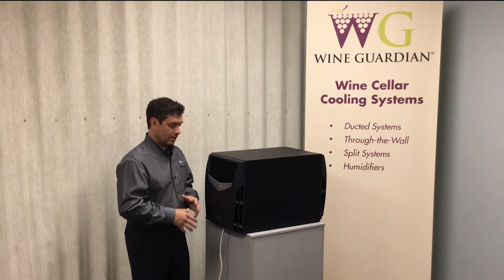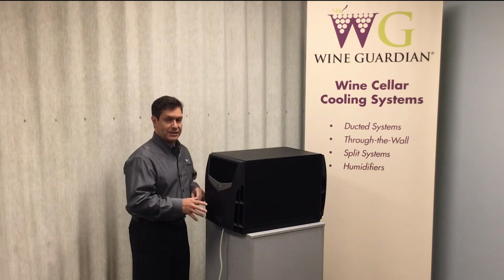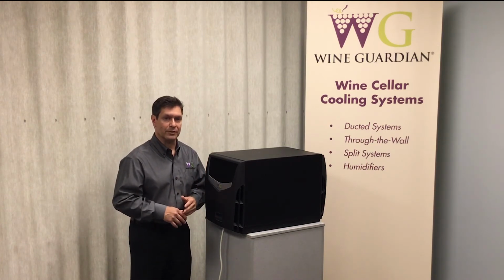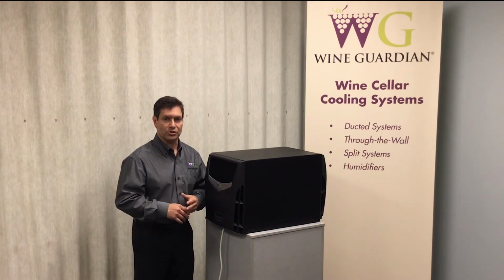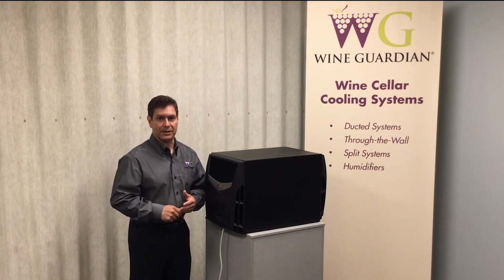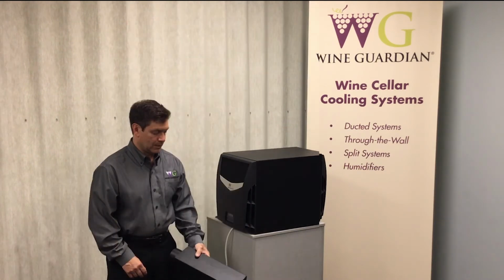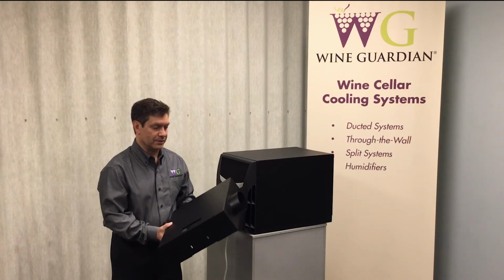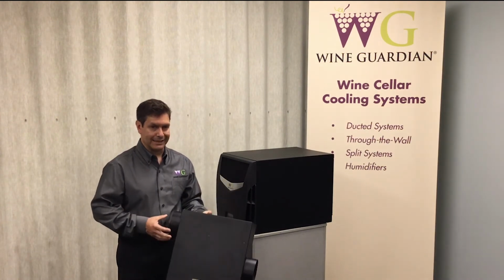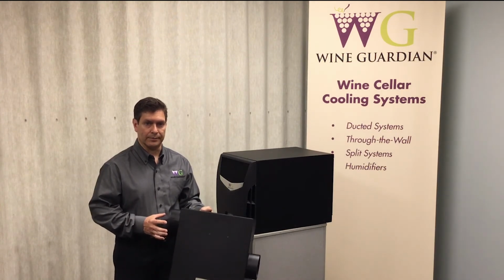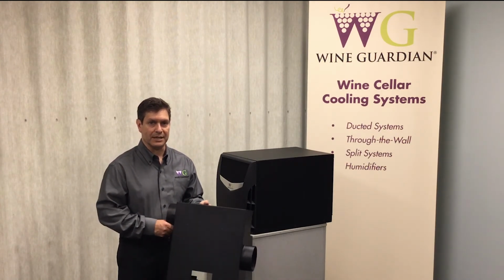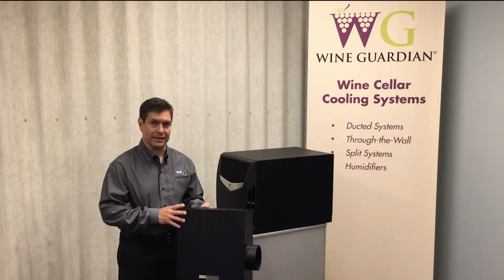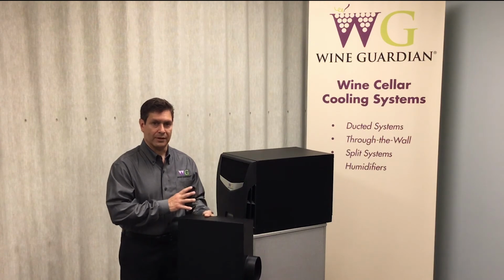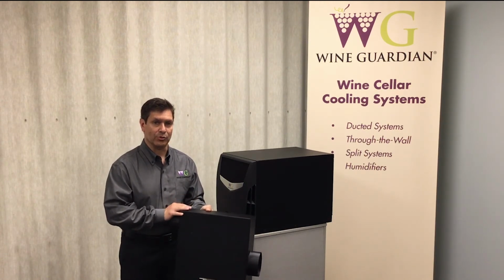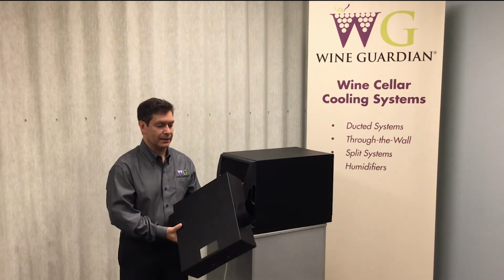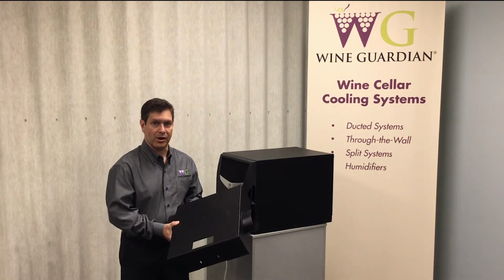We've had a lot of applications where we've connected up the duct collars and we've got the serving temperature option. We're controlling into the low to mid 40 range for maybe white wine storage or a serving temperature application scenario in a restaurant or a home. One other thing I want to point out with regards to the duct collar connections, these are to be used with a limited amount of ductwork. Probably a maximum of 12 to 15 feet of ductwork is allowed on these types of connections. The fans inside the unit just don't have the capacity to move air through a lot of ductwork. So just be careful how much ductwork you're putting on the ductable connections that we offer.